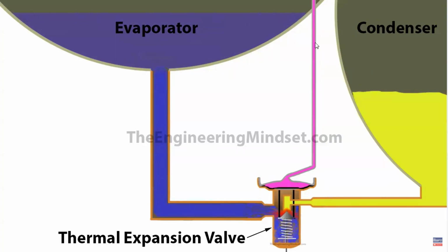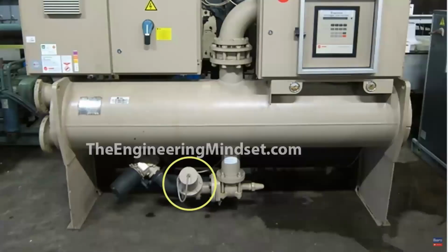And finally, once the maximum amount allowable superheat is there, the valve body opens fully, allowing the maximum amount of refrigerant to flow from the condenser through into the evaporator. So this type of expansion valve is exactly how you would find in a kind of household air conditioning unit, but the valve is just a slightly bigger version, obviously to handle the cooling load, which it needs to for the size of the chiller. The third expansion valve we're going to look at in this video is the electronic expansion valve. Now, in the real world, the electronic expansion valve will look like this. You can see it highlighted in the circle here. Now, this type of expansion valve gives the best performance.